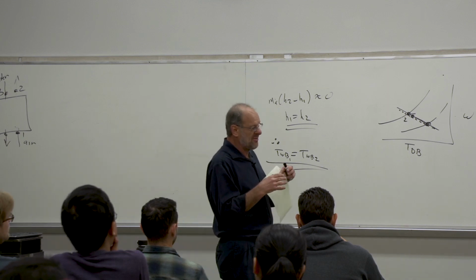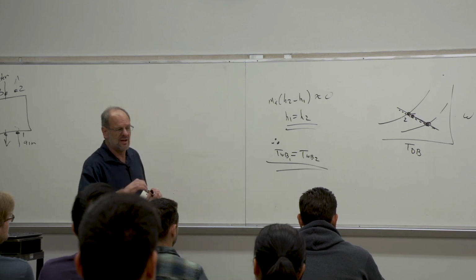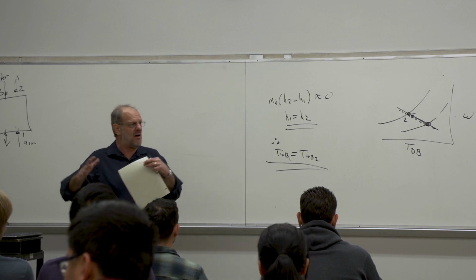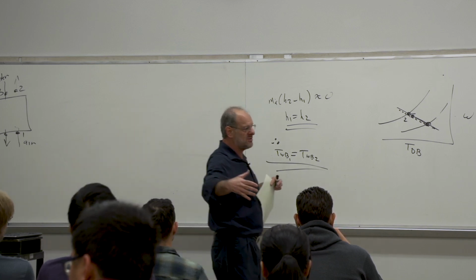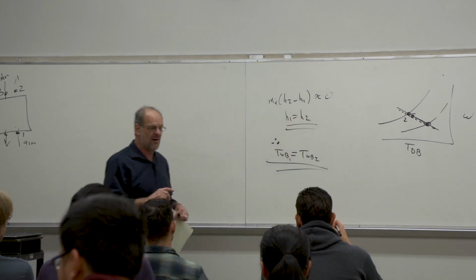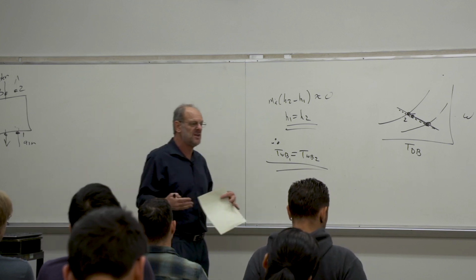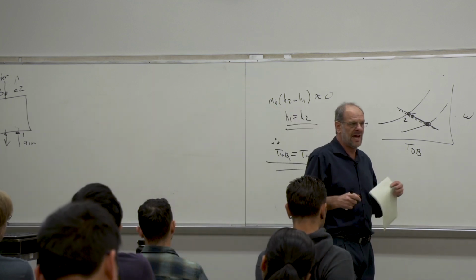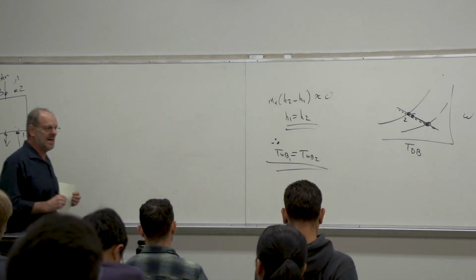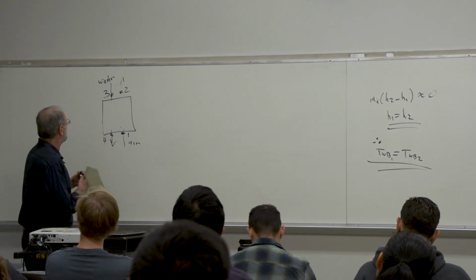But nonetheless, the cooling towers there are typical. On the larger units, which are only about 300 megawatts, which is about 1/4 of the size of a modern system, the cooling towers are about 100 yards long and about 30 yards wide and about 5 stories tall. And that's just for one 300 megawatt power plant, okay? Imagine what the cooling tower would look like at a typical 1,200 or 1,500 megawatt electric power plant. Your cooling towers are going to be hundreds of yards long, stories high, massive devices, okay? Again, they're everywhere. You'll see those jumbo cooling towers the next time you drive by Etiwanda.